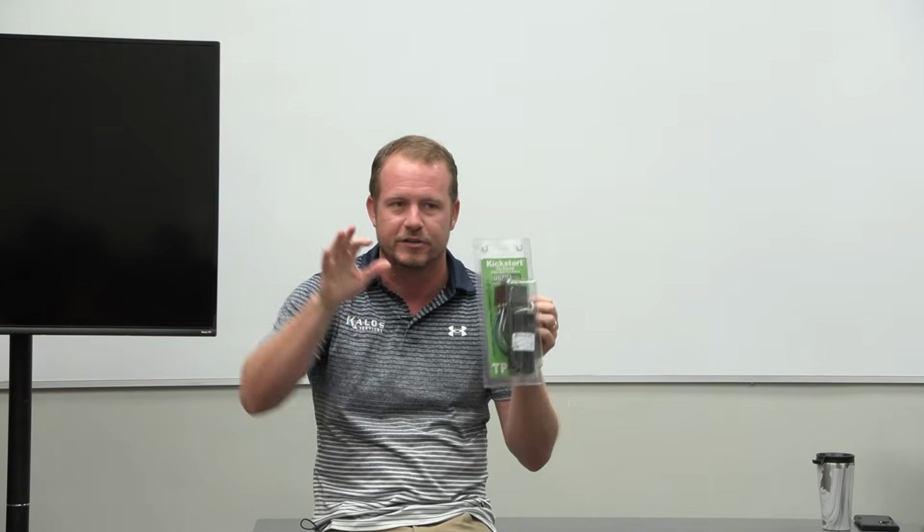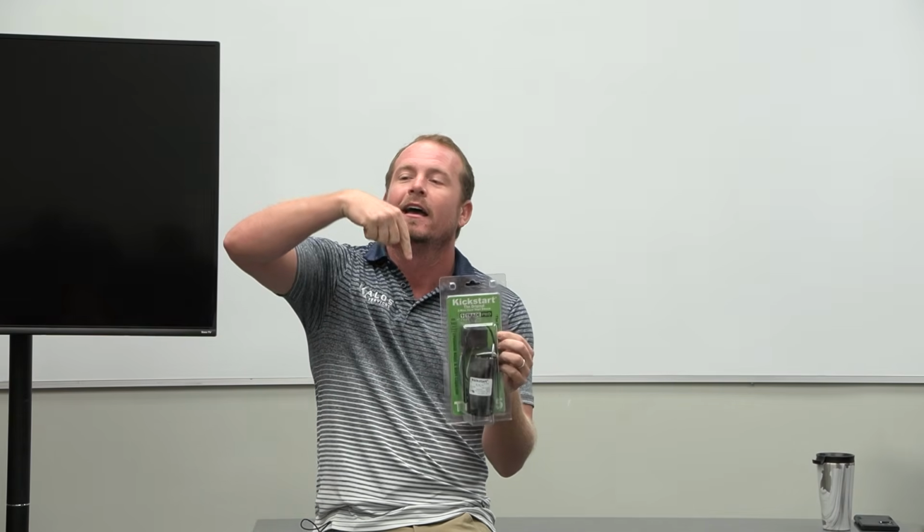It's not because there's anything wrong with the aftermarket hard start kit. There's nothing fundamentally flawed about an aftermarket hard start kit. It's just that the capacitor and the relay have to be designed for a wide range of compressors. They're not designed for this specific compressor. And so what that means is that either we're underdoing it or we're overdoing it. And there's two ways to underdo it or overdo it. One is, because this relay is designed for when that compressor gets up to about 80% speed, and that has to do with what we call back EMF, which means that, just quickly for those of you who are nerdy and want to understand how this works, I saw your face light up.